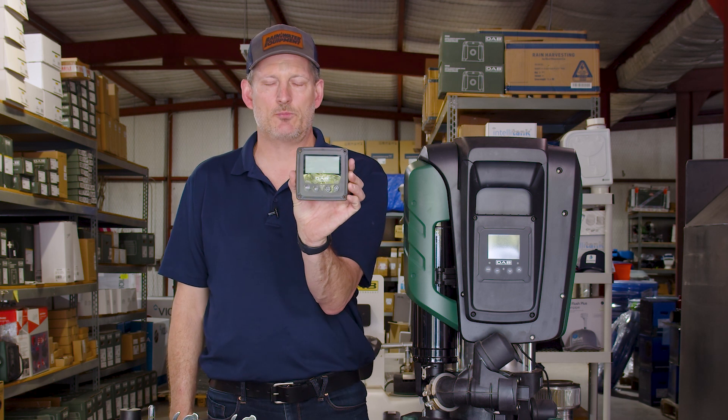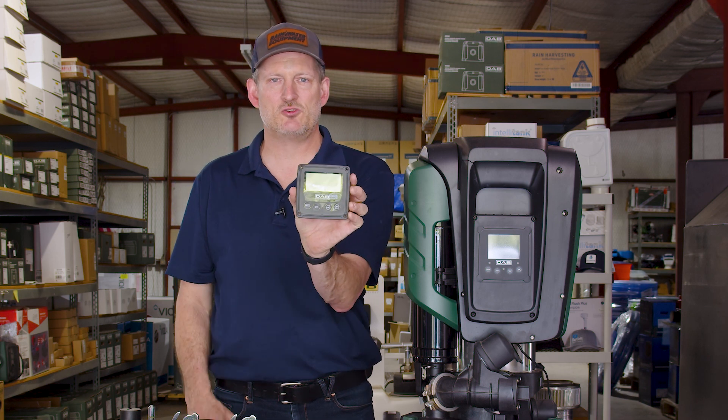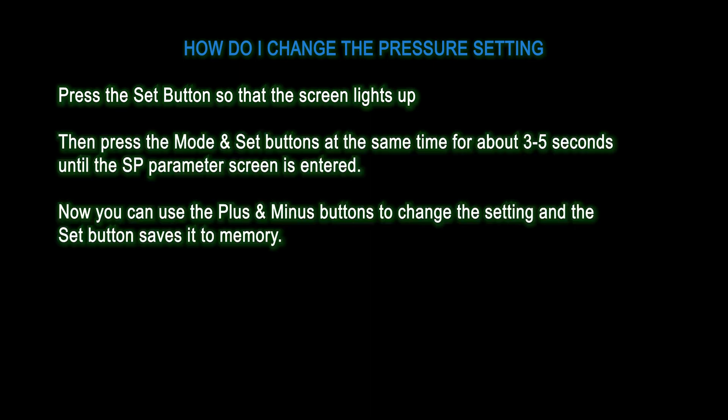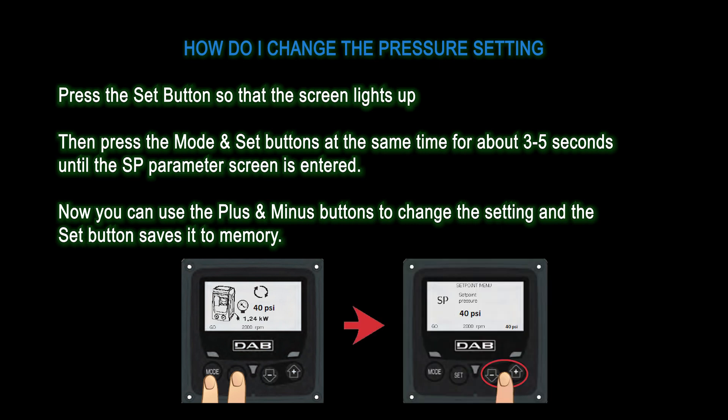There's a screen on the pump consistent with the entire line of Easy Line products from DAB, where you punch buttons to make pressure changes and other settings. To change the pressure on this pump or any Easy Line pump, hold down the Mode and Set button for about five seconds — SP will come up on the screen. Then use the up or down arrow to get the pressure setting you want and hit Set.